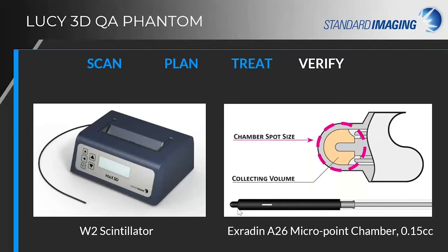The Exradin A26 is also uniquely designed with low Z materials, making it the only reference class micropoint chamber on the market without, excuse my highly technical term here, the wonky effects that other micropoint chambers available on the market have.